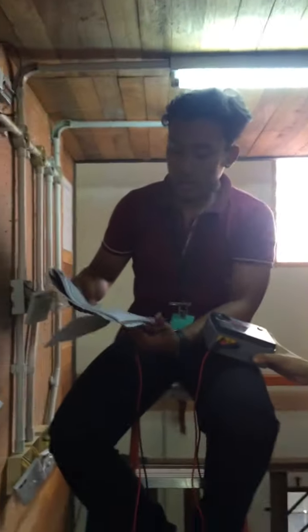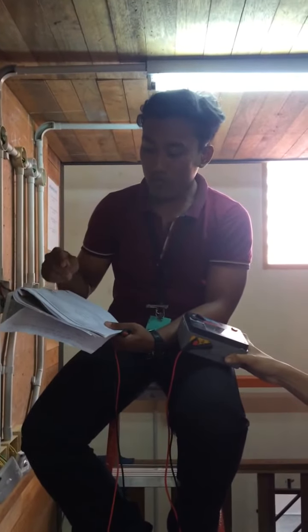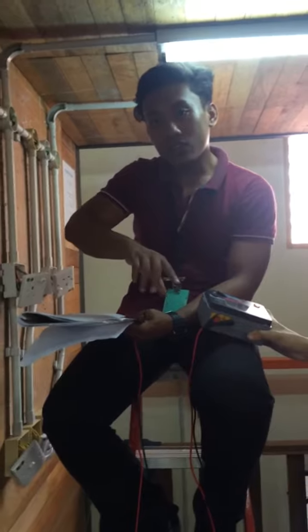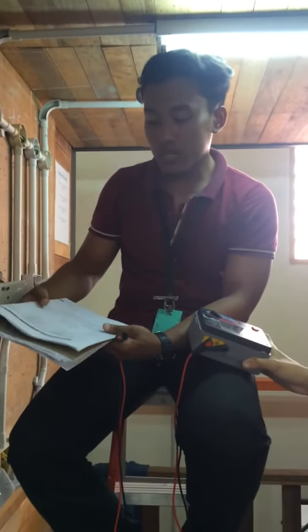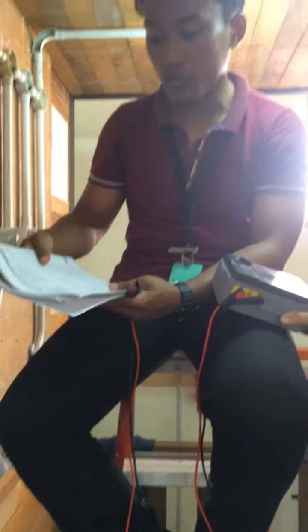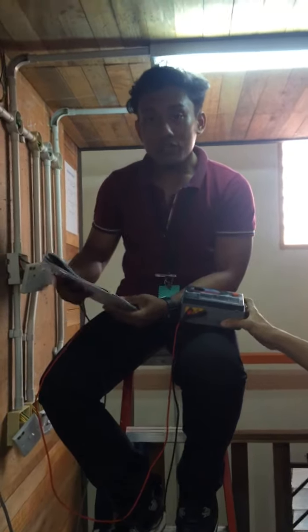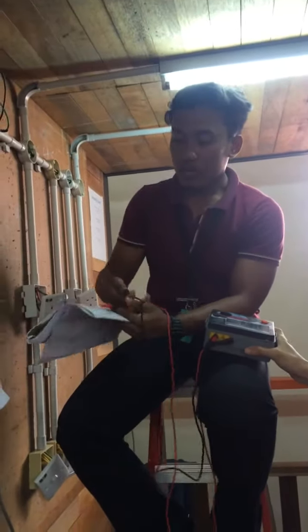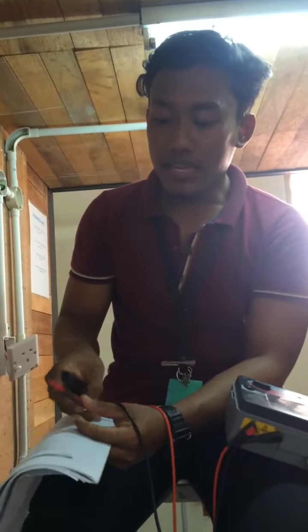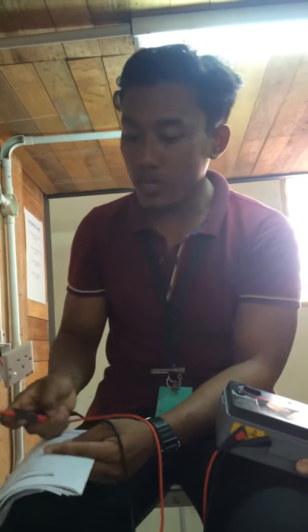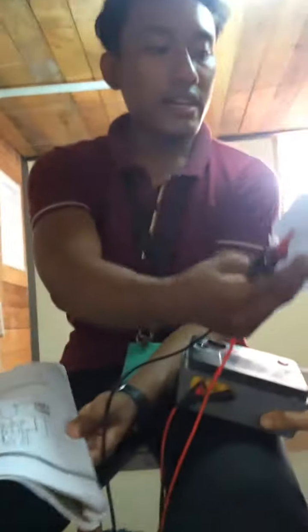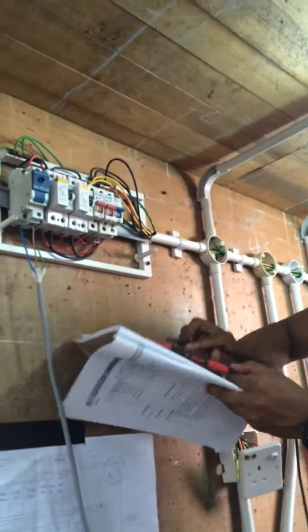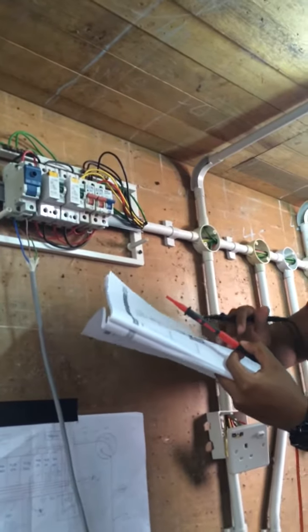The reading value must be more than 1 meg ohm for different polarity. So I will do the test after this. And lastly, for the same polarity, the reading value is less than 1 meg ohm. Okay, let's continue the test. So this black probe is for earth and this red probe is for line. I will follow the diagram given. So I will test point live to live first. For the same point, the meter reading must be lower than 1 meg. So the circuit condition will be good.